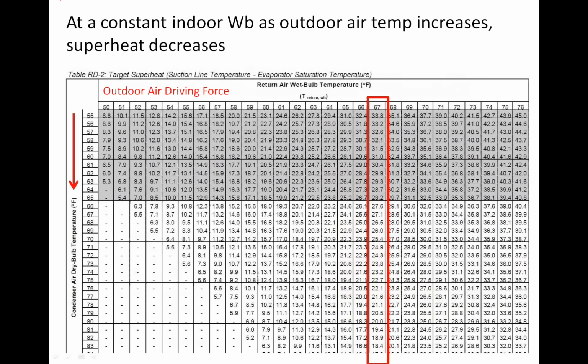Okay. So if we're looking at a constant indoor wet bulb temperature, as the air temperature increases, this would be the evaporator side, right? Sorry, at a constant wet bulb, 67-degree wet bulb. As we increase our pressure on our condenser, air entering dry bulb temperatures go up. So you start here at 55, our target superheat's 33.8, right here, 33.8. So it's 67-degree wet bulb, 55 degrees outside, target superheat's 33.8. If we increase that to 65 degrees, well now we're at 28 degrees. When we increase the pressure on the condenser, we're driving more refrigerant into the evaporator, and the target superheat's going to go down, right? Pretty simple.